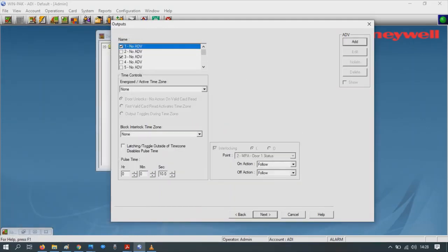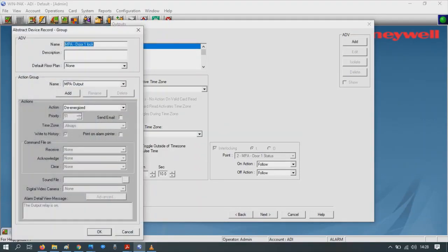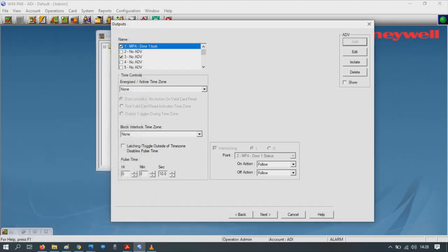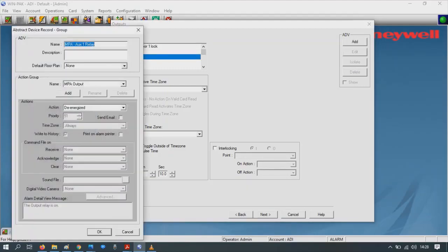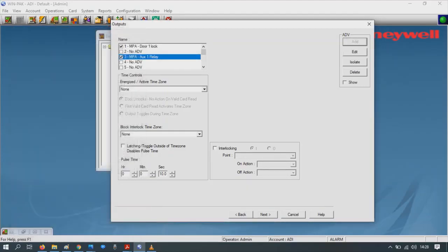Outputs: this is your lock output. So for door 1 lock output, you click Add on ADV, make sure it's OK. Number 3 is your door status output, maybe a local alarm if you're going to use that. Add and press OK.